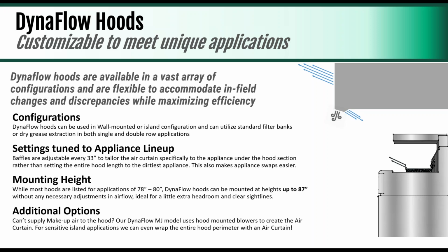The way that the makeup air is done is we can actually tune it over each appliance. So we can open and close some dampers inside the hood to increase or decrease the amount of air curtain. And that's just because different appliances require different levels of an air curtain to be effectively captured. The mounting height, we mount everything all the way up to 87 inches above the finished floor. Most standard hoods are listed for anywhere between 78 to 80 inches above the finished floor. We listed ours a little higher because we find we have more and more requests to go higher.